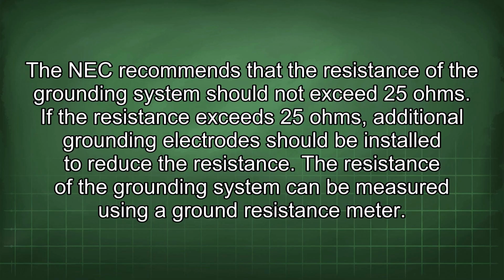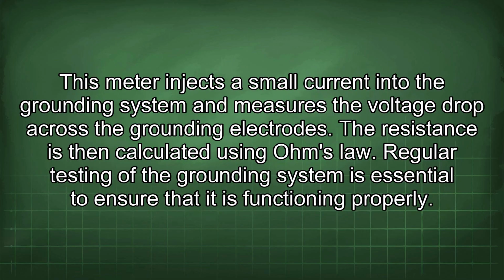The resistance of the grounding system can be measured using a ground resistance meter. This meter injects a small current into the grounding system and measures the voltage drop across the grounding electrodes. The resistance is then calculated using Ohm's law. Regular testing of the grounding system is essential to ensure that it is functioning properly.